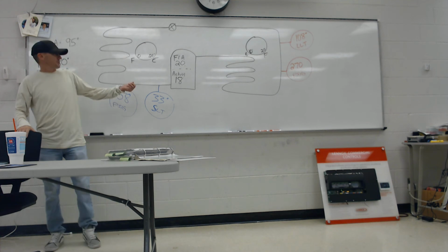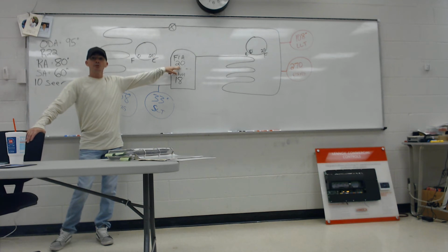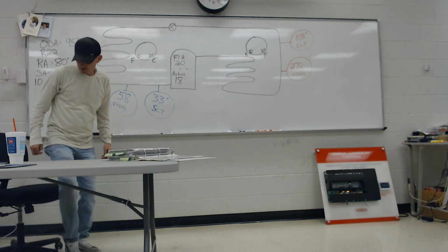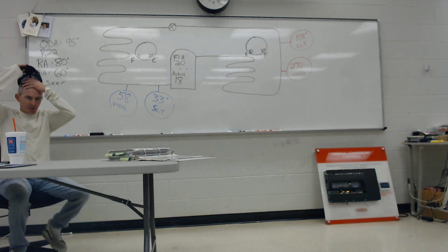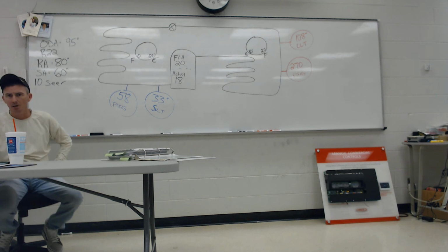Hey, if you have a compressor that's rated for 20 amps, when does it pull 20 amps? At startup it'll pull locked rotor, more than that. Under full load, 105 degrees, which is usually like 105 degrees outside. And I'll be honest with you guys, some of these new compressors, especially with all these 80 microfarad run caps now, they're expecting a lot out of the start winding, and I don't know if it ever pulls FLA.